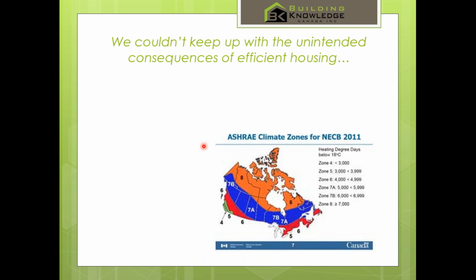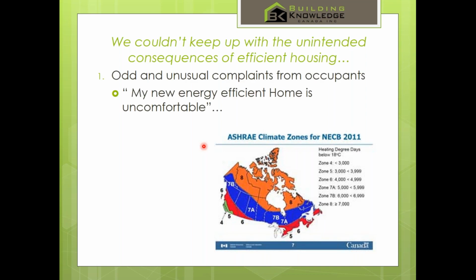And what we started to see happen is when you cannot account for things like heat recovery, and you cannot adequately reflect low air leakage in your heat loss, heat gain models, and you cannot adequately account for below grade heat loss or for ventilation, then when you start to increase these things in new homes, the old way of doing calculation simply doesn't work anymore. And we started to see this, what we call unintended consequences in efficient housing, back in, I'm going to say 2007, 2008. Those were some of the early days of seeing Energy Star homes in Ontario.